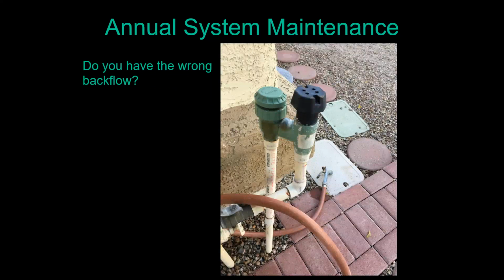Okay. What you want to make sure you're not doing is using the wrong type of backflow preventer. So this particular backflow preventer is what we call a manual anti-siphon valve. There is a little check valve down here where, if the water's trying to run backwards through the system, it opens up and creates an air gap. The problem is it's got irrigation valves downstream that are shut off, which means that little check valve will never open up and allow that air gap to be sealed. So if you've got one of these and you've got your irrigation valves down underground in the boxes like I'm showing here, you want to get that replaced with that pressure vacuum breaker. Being code is probably the least important reason for you to make sure you're doing that. It really is about the safety of your drinking water.